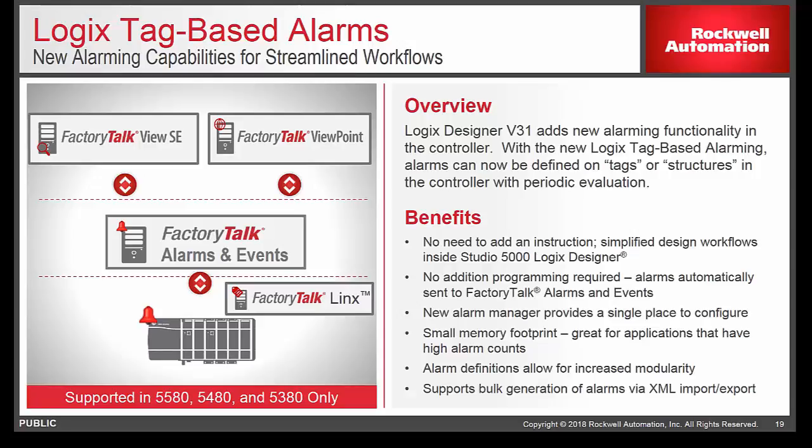Alarm timestamping, acknowledgement, resetting, as well as the entire alarm message would then be managed inside the Logix engine. With version 31, we've added a new method to manage alarms in the controller with much simpler configuration on the tags themselves versus the program solution with those 2 instructions. This means that you're no longer adding those instructions to the code, so there's no additional programming required, and there's a new alarm manager that gives you a single place to configure all those alarms inside the Logix design environment.